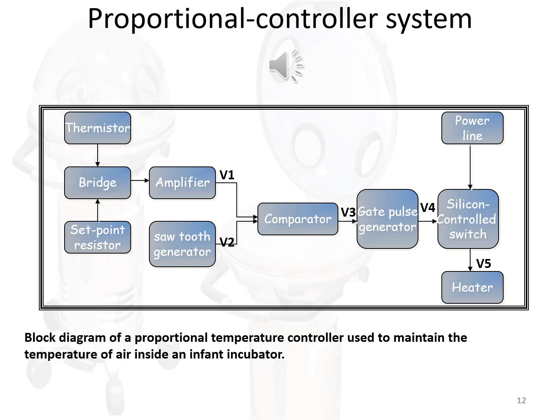A thermistor is a type of resistor whose resistance varies significantly with temperature. The control system uses the thermistor in a bridge circuit with the set point resistance as another arm of the bridge. When the temperature is equal to the set temperature, R thermistor is equal to R set point, and the bridge output equals 0. When the temperature is not equal to the set temperature, the bridge output is amplified, giving the voltage V1 at the output, which is proportional to the difference in temperature between the thermistor and the set point.